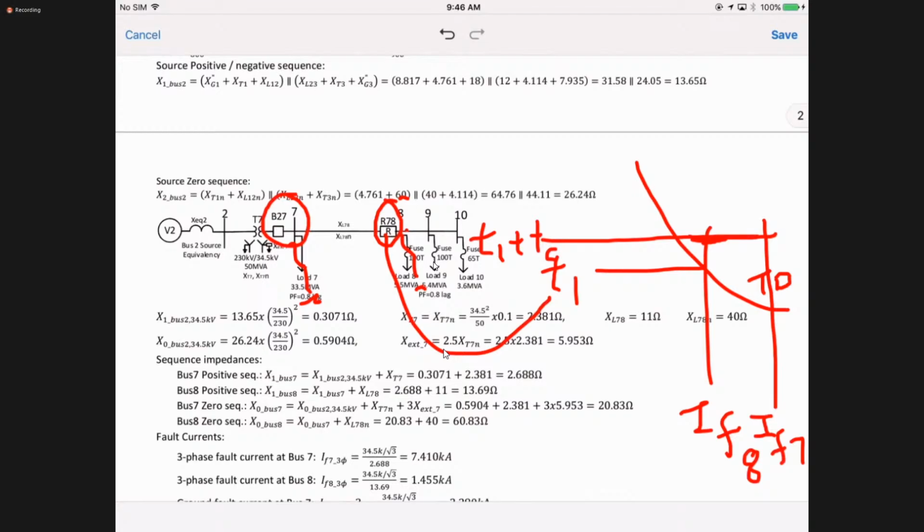You will say, oh, this doesn't work, because from this time you add the coordination, then it will operate here. Then you have to react faster because it's a larger fault, so you have to pick another curve, such that it will operate earlier.